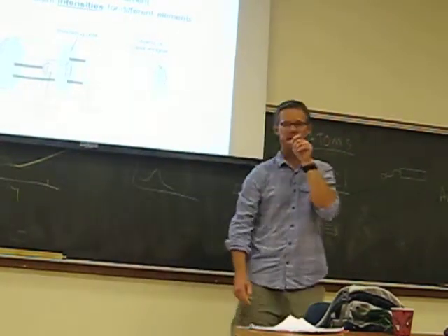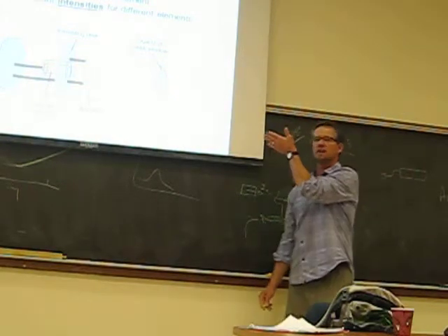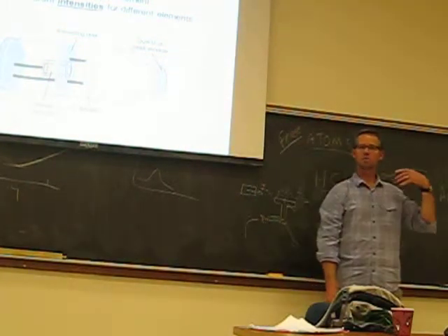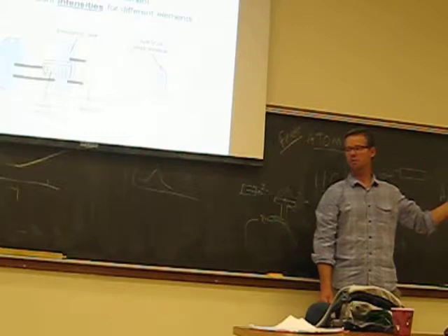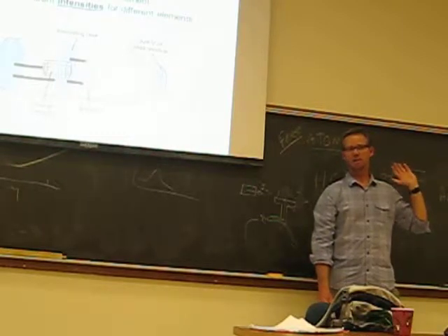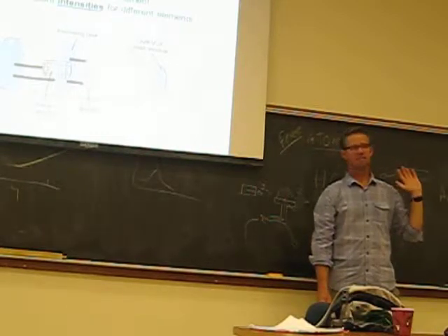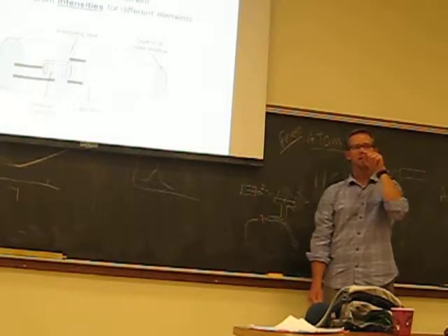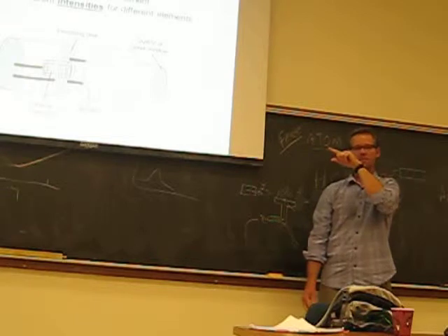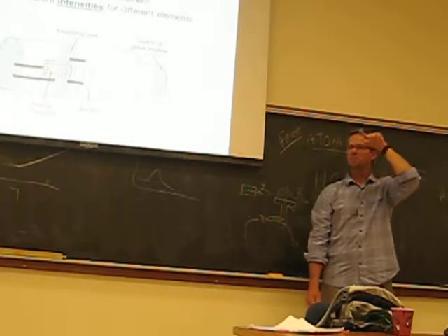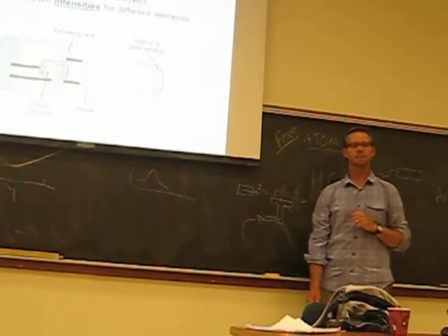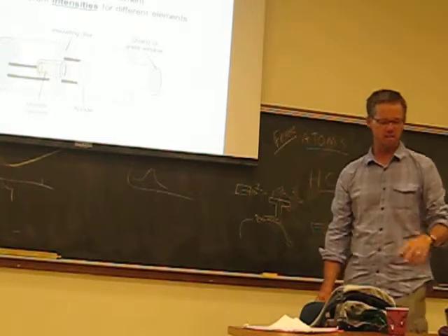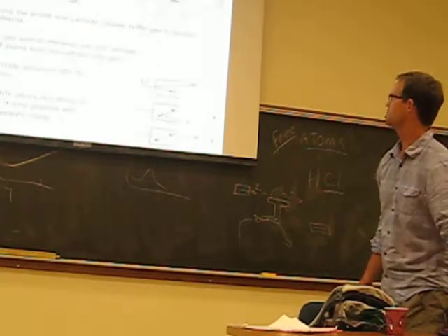That's how we generate it. And so the advantage of a hollow cathode lamp, as opposed to what we used in UV-Vis spectroscopy, which was a deuterium arc lamp, is that the hollow cathode lamps, with a specific cathode element, generate a very specific spectra for that element. Okay? And that's very important in atomic absorption. We'll talk about why that is.